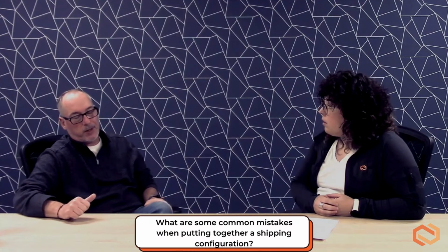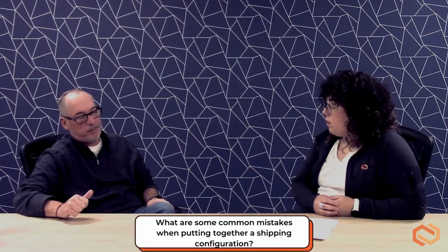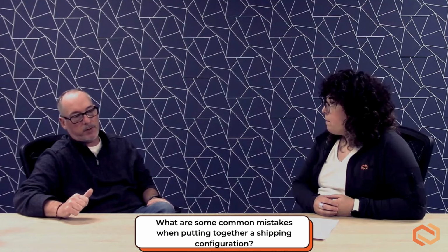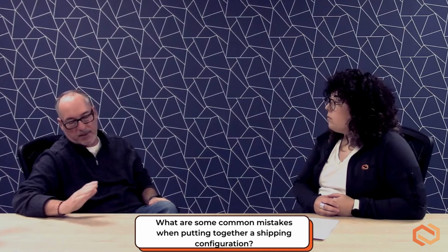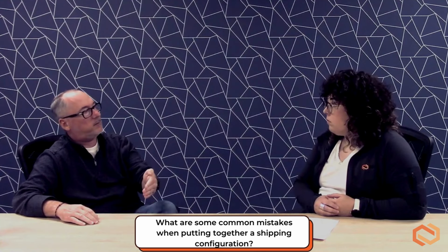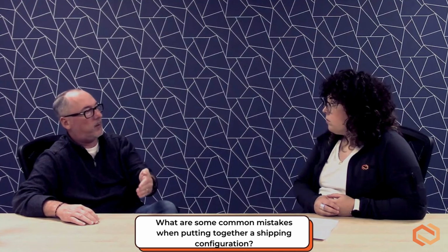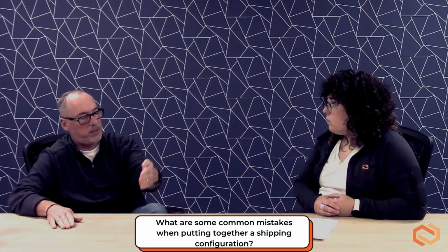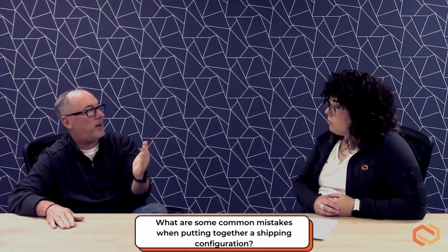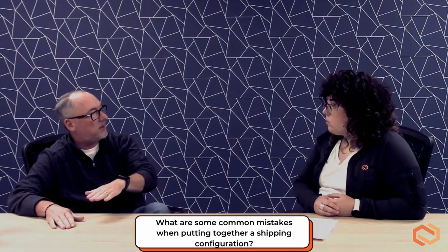Sure. So, all right, now we're feeling a little more confident with our sterile barrier system and our process validation. What are some common mistakes we see when clients are putting together their whole shipping configuration? The shipping configuration, I think, is paramount, right? Let's say I'm dealing with a heavy product, it's in a tray, and the overall orientation, right? I think that's key. Let's say you're side loading these and you've got a heavy product. Well, you're primarily going to run into issues because that's not the bottom orientation, and your sample's oriented on its side or on its end, right? You ideally want these on the bottom orientation.